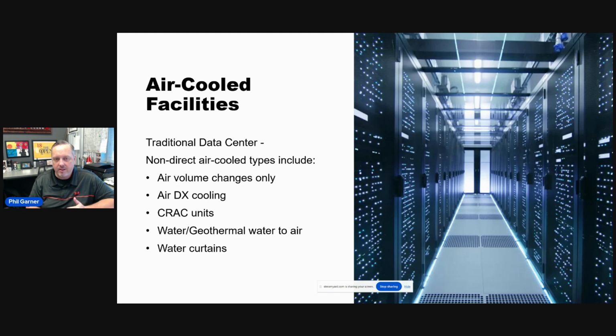When they say this equipment can only work from temperature X to temperature Y, you may want to get one and test it to see what you can really do with it, to see how high you can get before the degradation starts. Because if you say, oh, I have to have DX cooling, that's an extreme cost difference to maintain. If you can actually get what you need without that, your ROI is going to be much better.